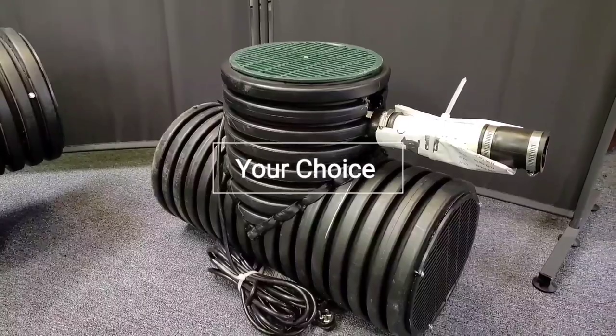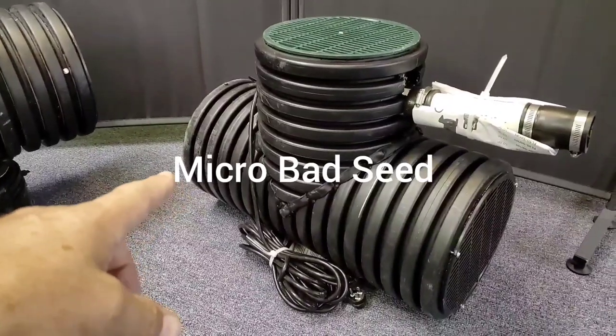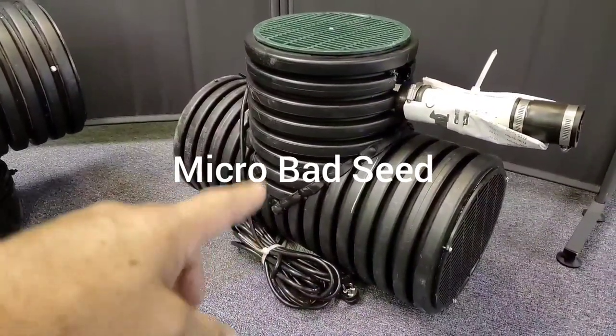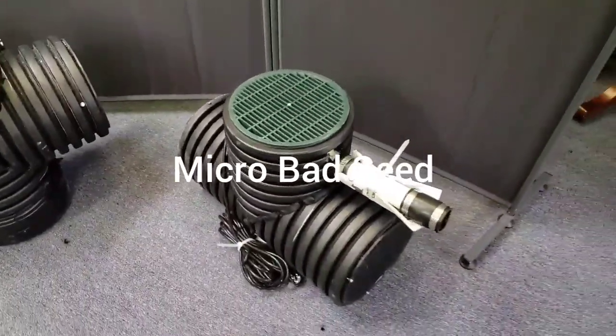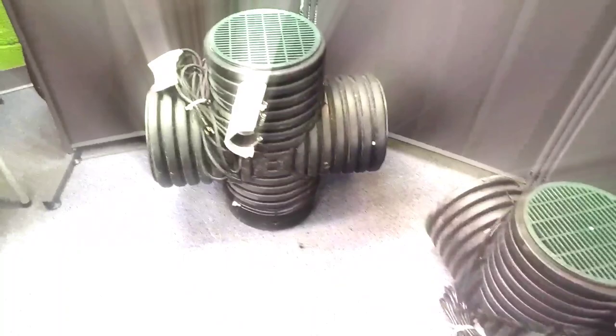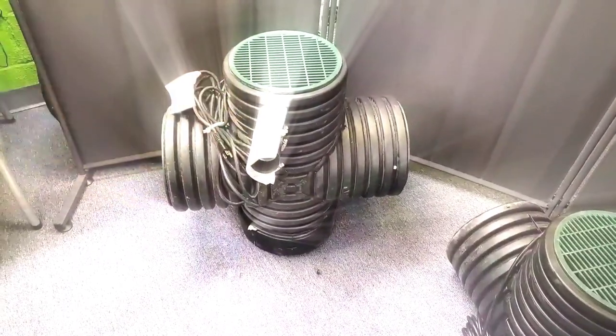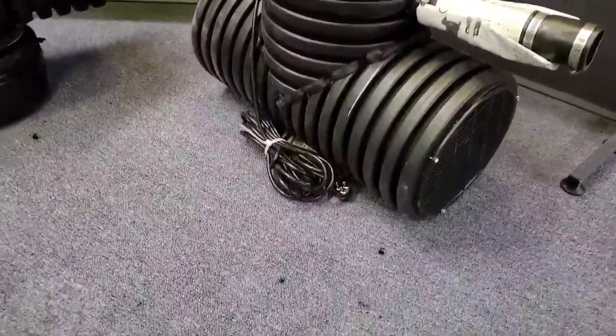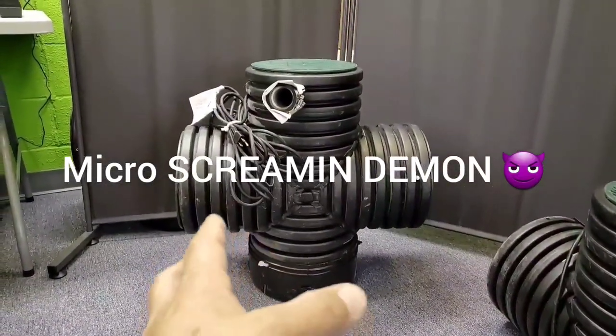The Bad Seed Micro — we could not fit a half-horsepower pump in this. So the Bad Seed Micro is a one-third horsepower, but it's 24 inches with an 18-inch dig, simply the easiest thing to install right here. So if your water problem isn't ridiculous where you need to pump 160 gallons per minute — Screamin' Demon territory — then the Bad Seed might work for you. It's super easy to install, and from an econ standpoint, it doesn't have the cost of the half-horsepower plant.